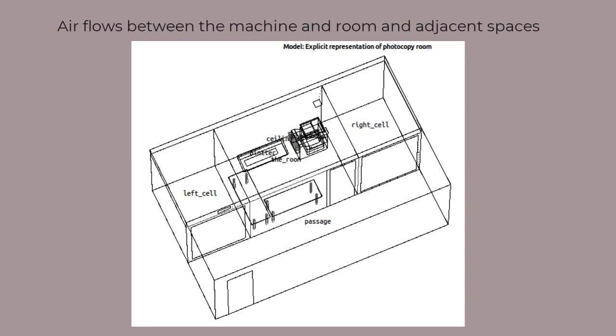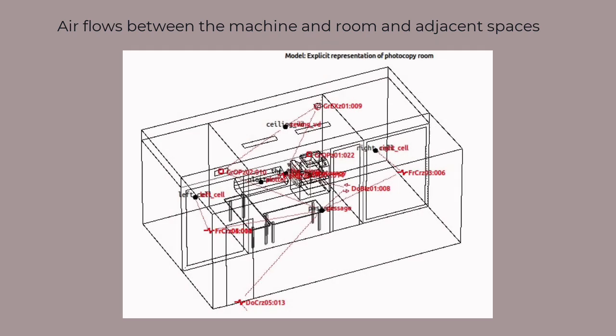One of the major heat flow paths is air exchange between the room and the photocopy machine. Observations indicated that the exhaust fan kicks on briefly during standby at roughly 40 degrees C. Observations also indicated heat from the print room dispersing into adjacent office spaces, so the digital twin uses an airflow network to track airflows between the rooms as well as between the machine and the print room. The latter is ideally controlled by way of a fan switch set at 40 degrees as an initial guess.